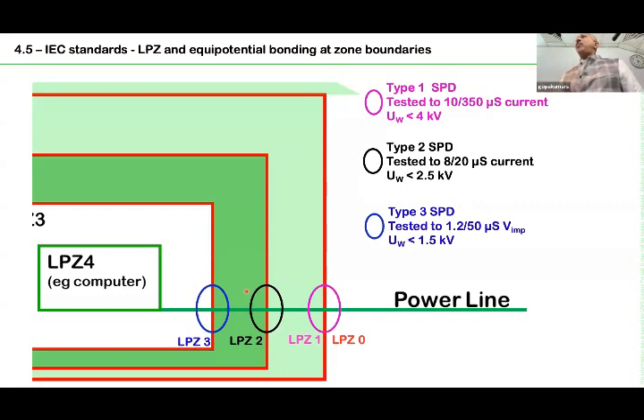That means the main distribution board has an SPD, the sub-distribution board another, and probably near the equipment you need one more. But all these depend on the type of building, size of the building, size of the electrical installation, and the way you routed the cable. You cannot apply the same principle for a small building as for a large building. That is not possible. We have to really analyze the situation and do it. So I would say this is actually an expert's job. You need the support of an expert to select this.